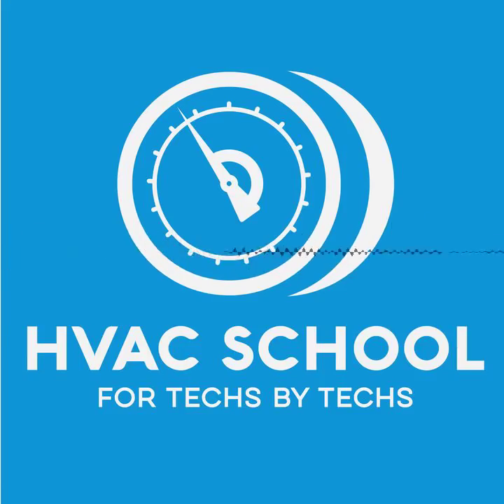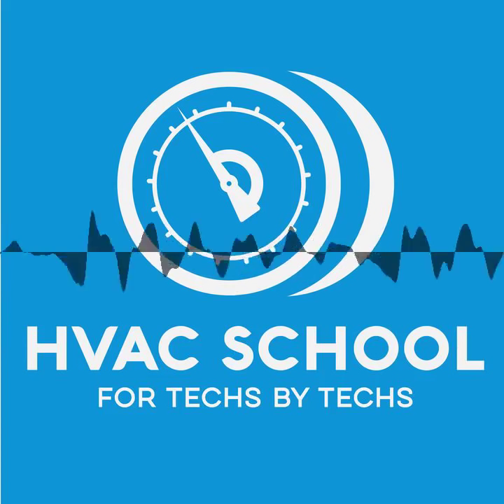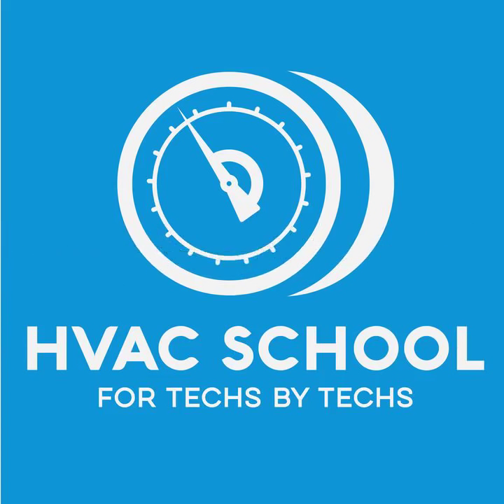So it can actually skip defrost and just keep running. But at the same time, a problem is, especially in restaurants that have a very high volume, that sometimes we need more defrost than that controller can handle, or sometimes we need longer defrosts. Typical strategy in a restaurant is to defrost for 45 minutes in the middle of the night when nobody's there. So that way we can really clear that coil of ice.